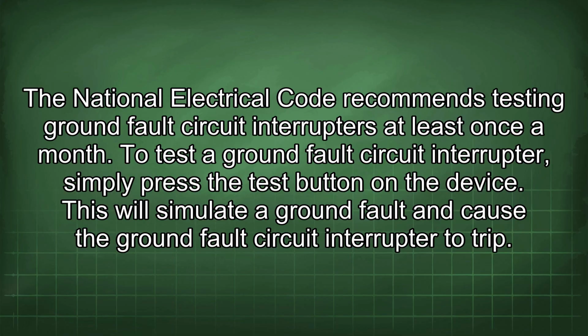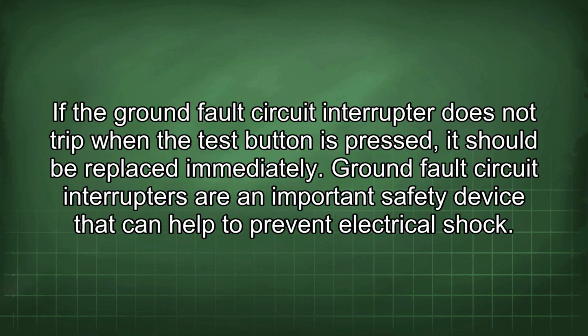To test a ground fault circuit interrupter, simply press the test button on the device. This will simulate a ground fault and cause the ground fault circuit interrupter to trip. If the ground fault circuit interrupter does not trip when the test button is pressed, it should be replaced immediately.